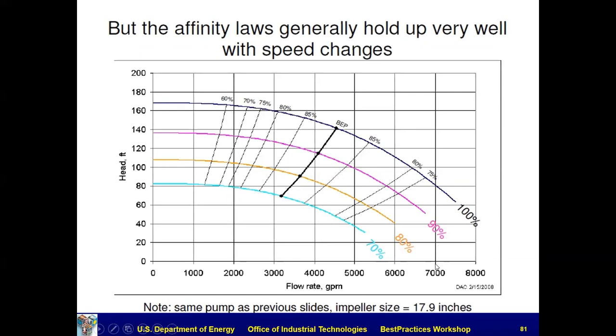So, you would say, okay, 7,000 GPM, I've got 80 feet of head. Put it in a table. 6,000 GPM, I've got 111 feet of head. Whatever. You pick all these points, you plot it up, and when you first look at it, it's kind of not so smooth. It's kind of bumpy.